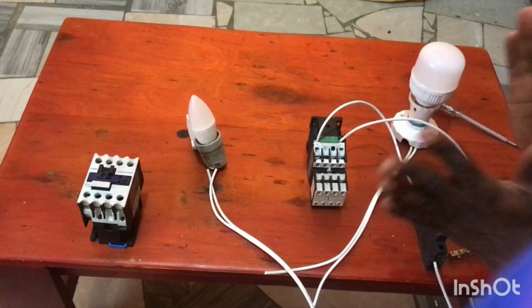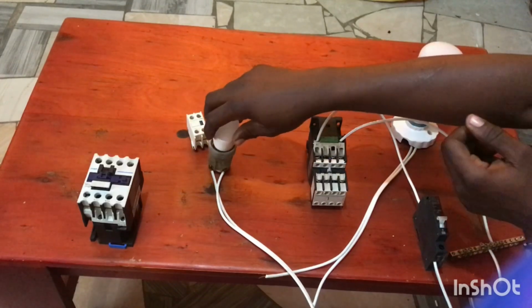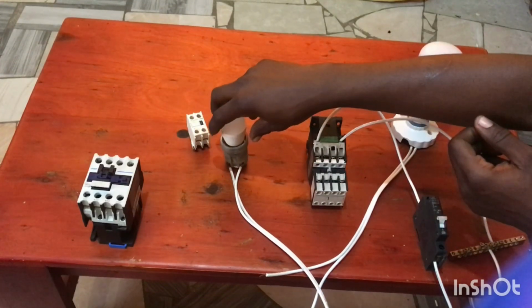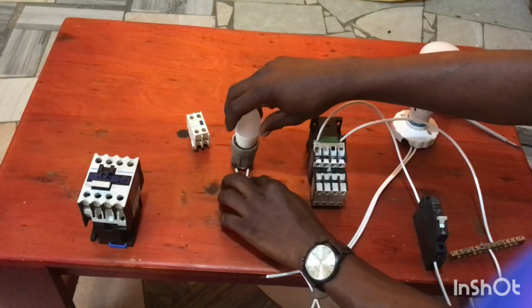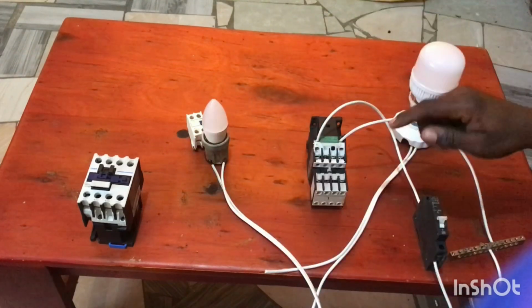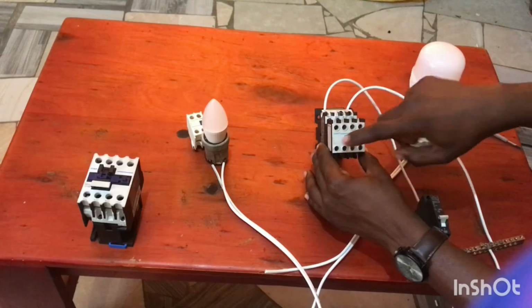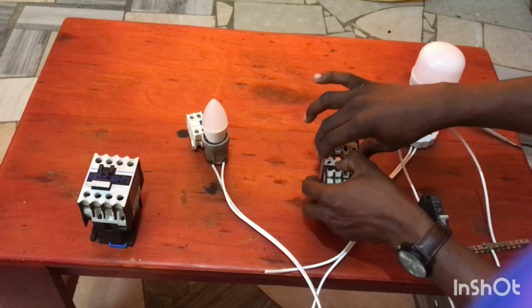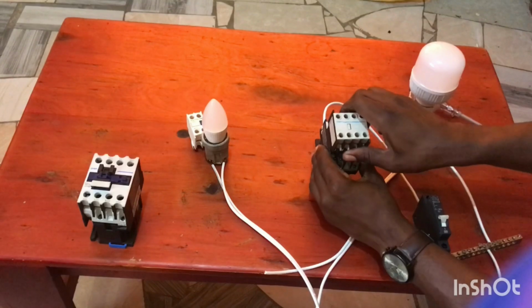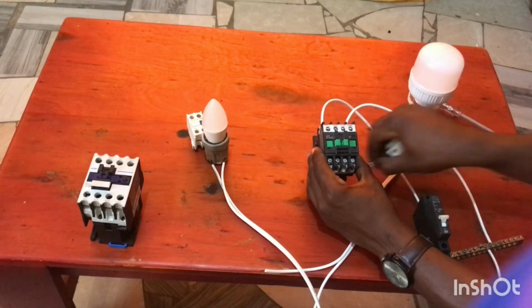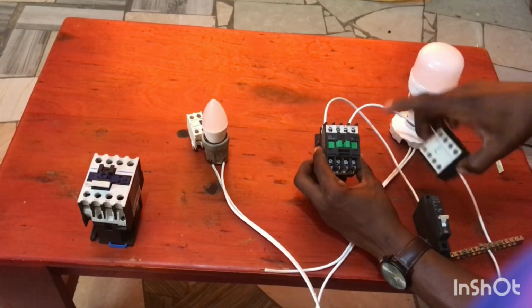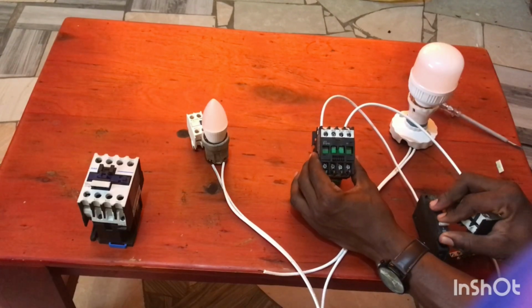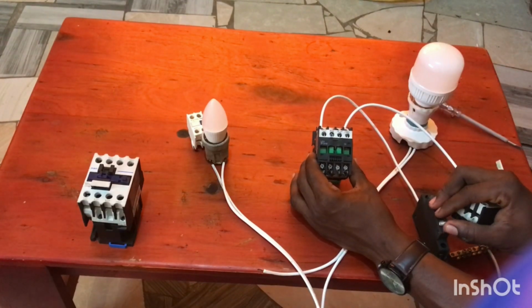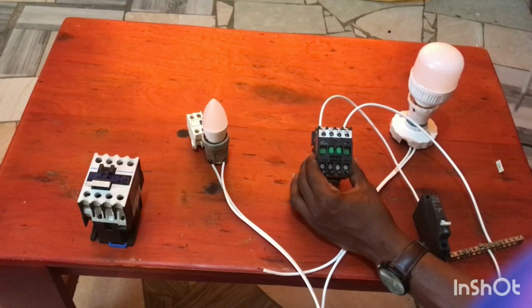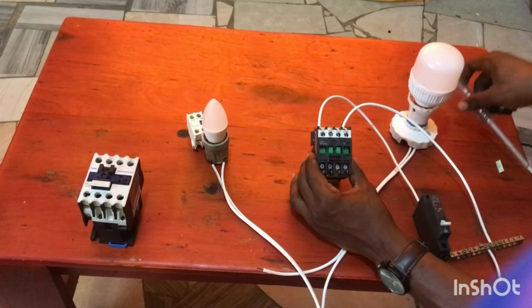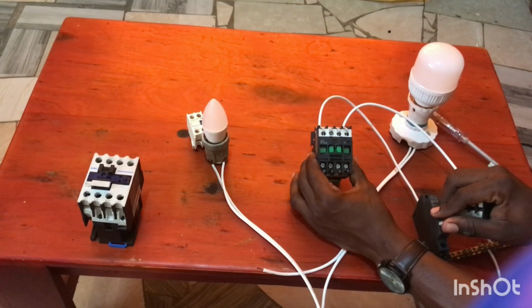So now let's see how these contacts work after they are energized. I'm going to use these two lights to show you how a contactor works. You can still energize the contactor without putting an overload and without putting an auxiliary relay. You can still energize it as it is, but we put this auxiliary relay just to increase the number of contacts.